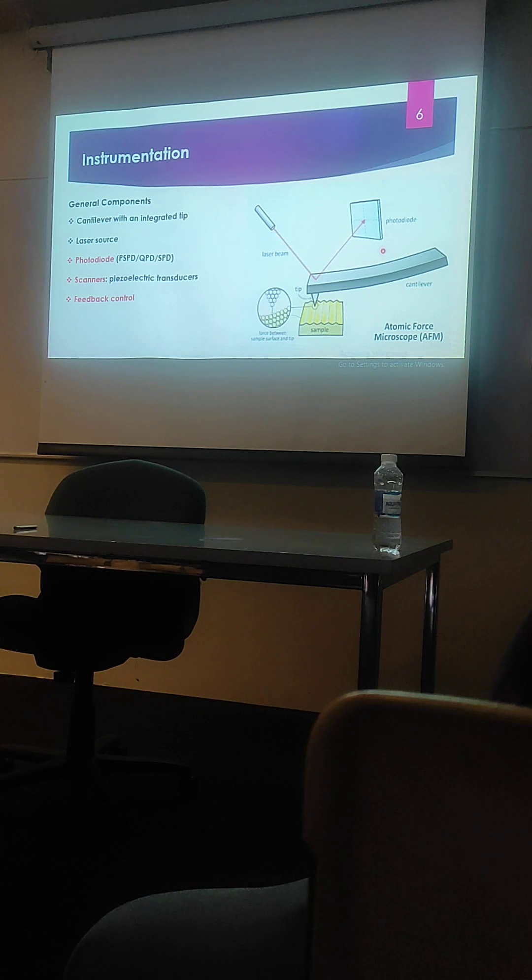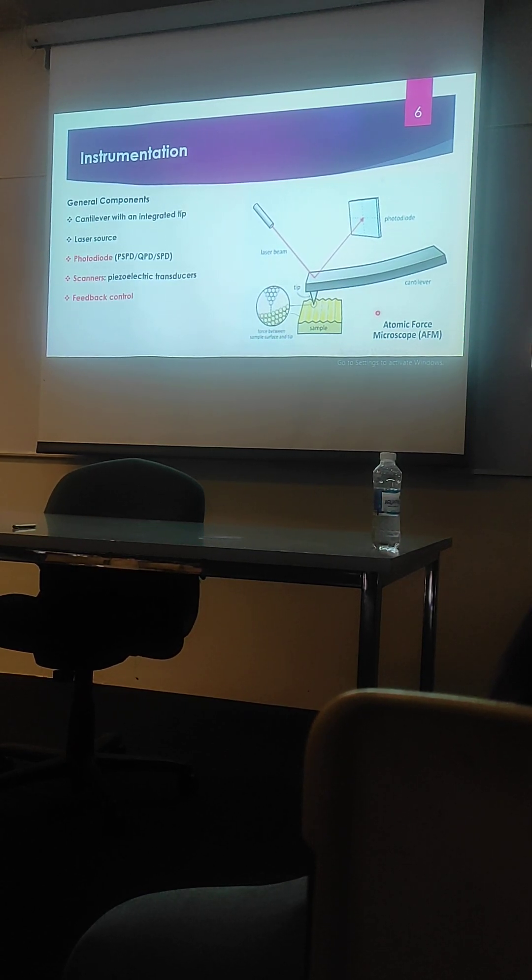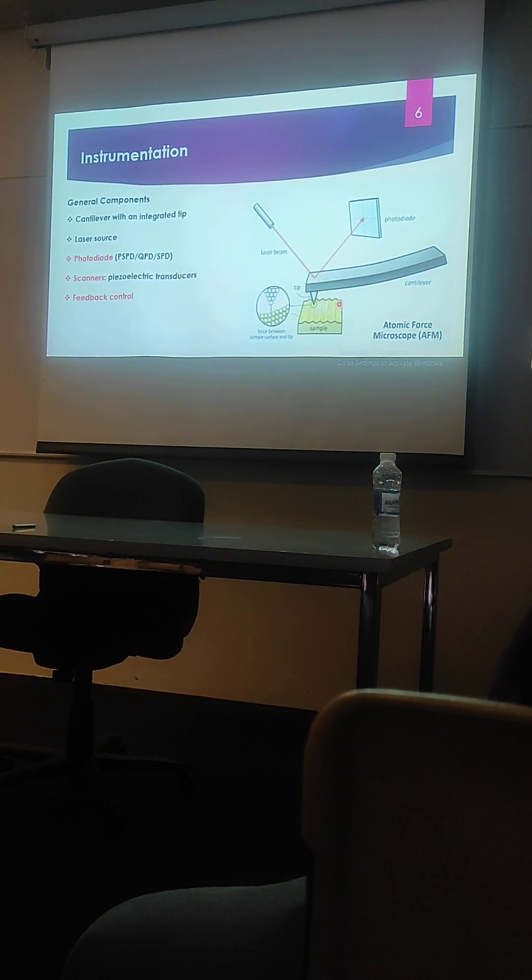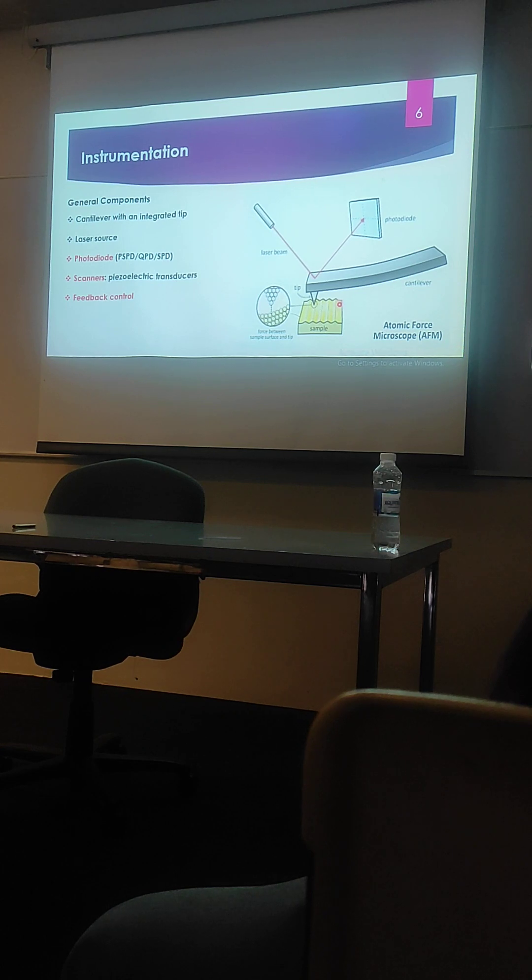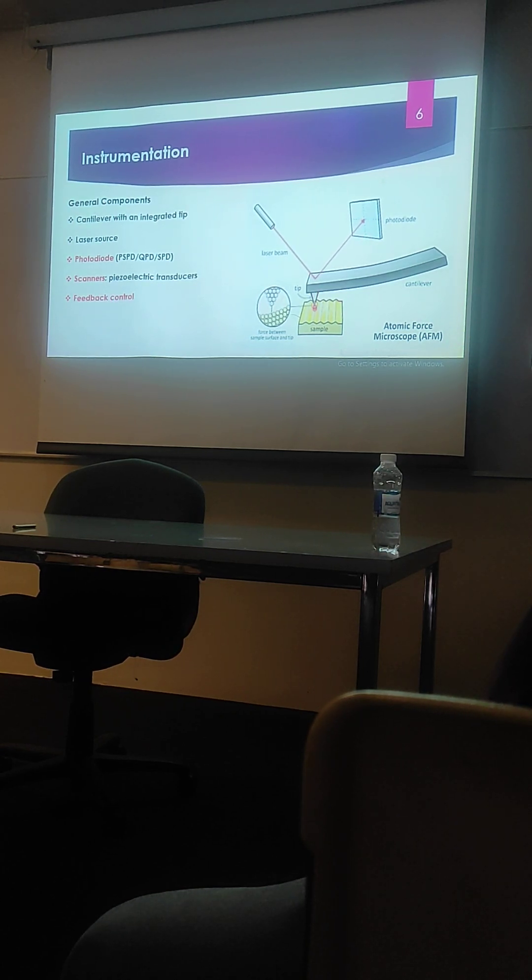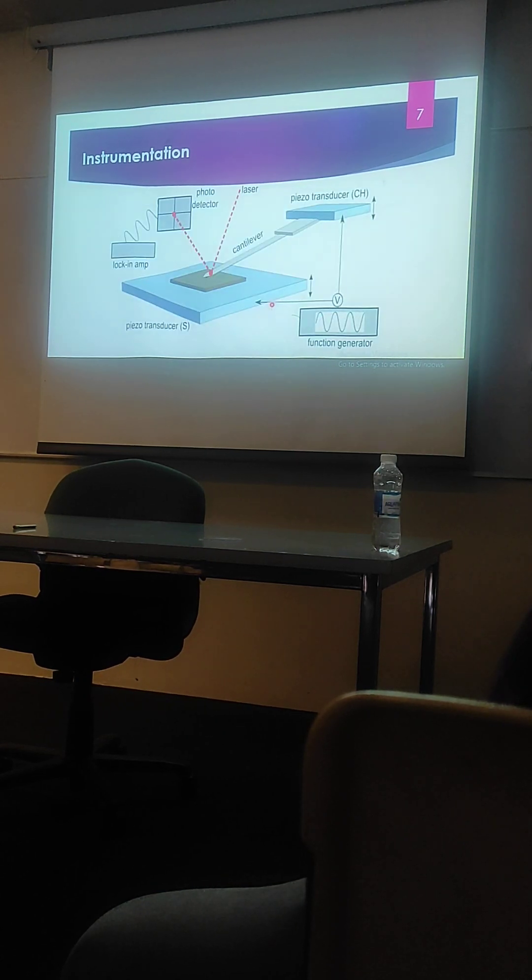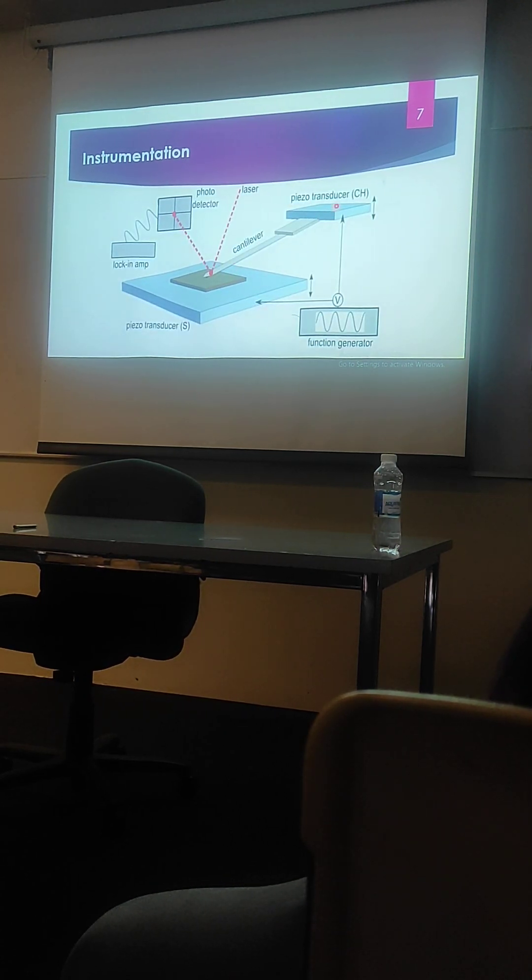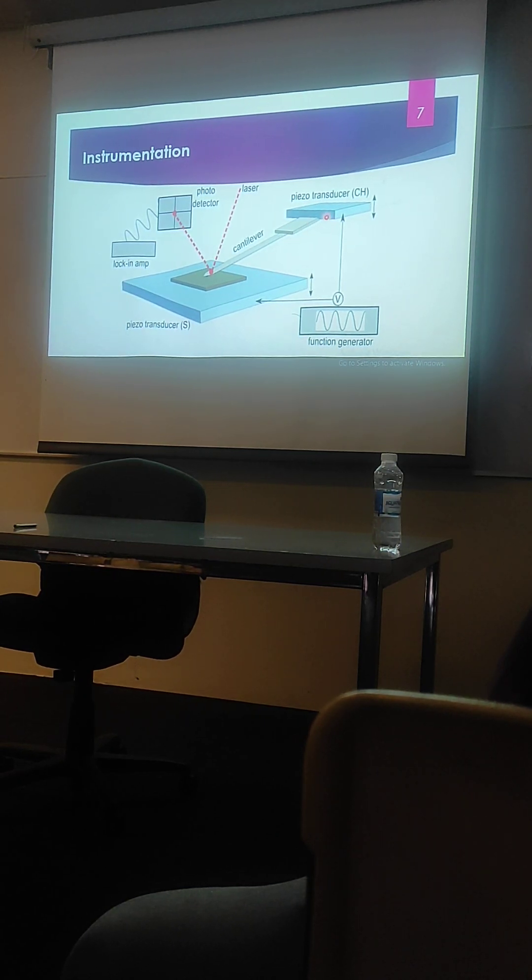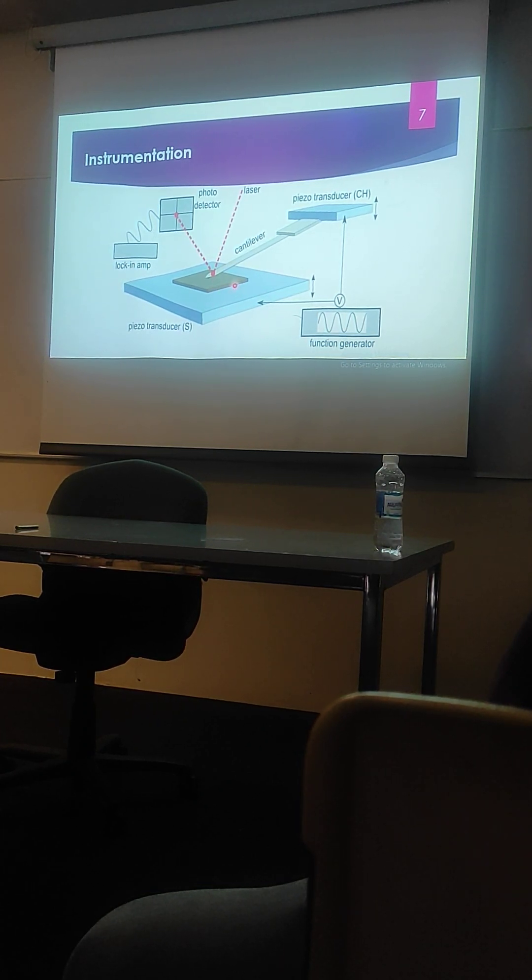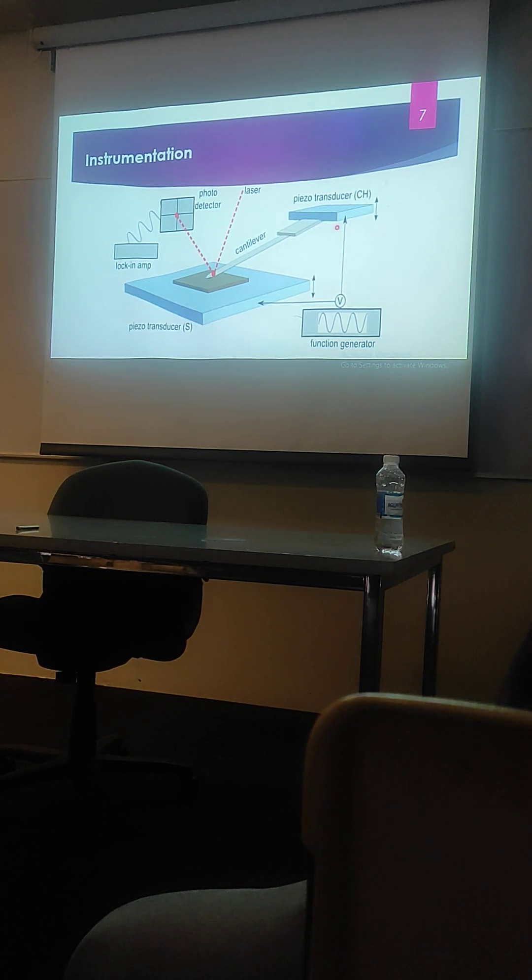A special class of transducers are used for scanning the sample surface, which are called piezoelectric transducers. And a feedback control system helps in maintaining the specific force between this tip and the sample surface. You can see here that these piezoelectric transducers are connected at the ends of this cantilever and as well as to the sample stage. It can move the sample in XY and Z direction as well as the transducer in these three directions.